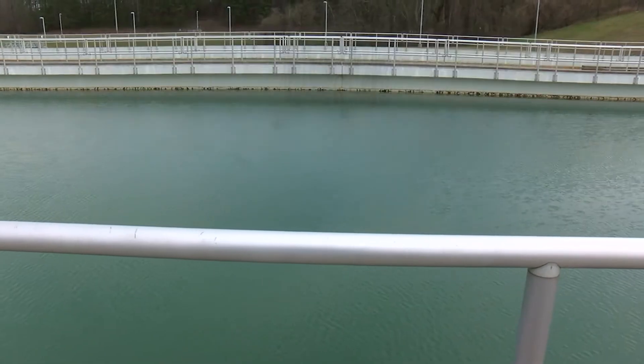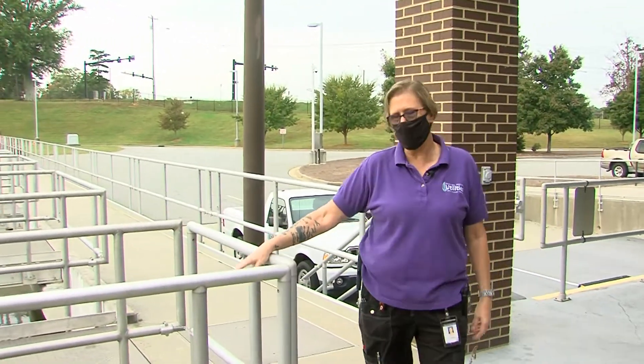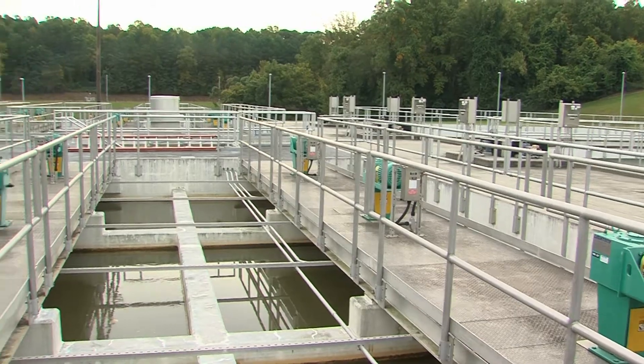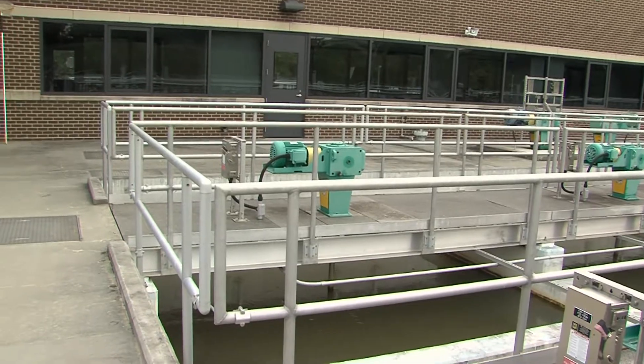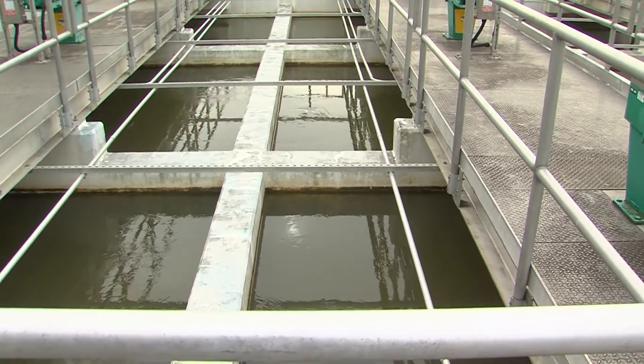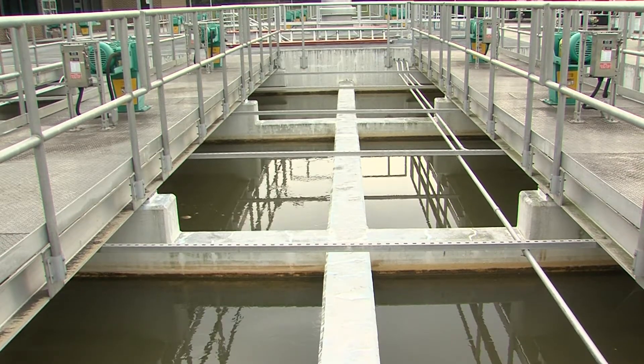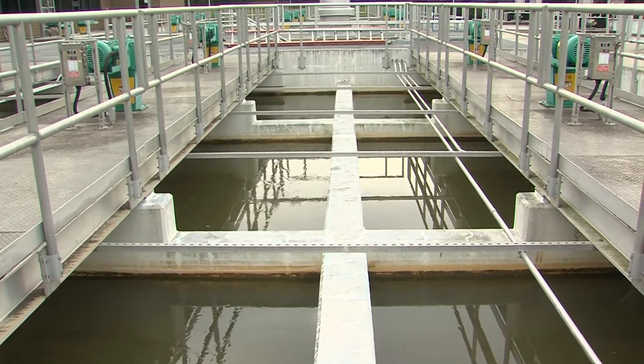This is where all the really cool stuff happens. Our first stop is the flocculators. This water is not ready for you to drink yet. These are flocculation basins. This process is actually stirring the water and the chemical together and causing a reaction in the water. The coagulation is actually chemistry at work — you're using positive and negative charges and making them want to come together and make bigger particles. This is the first stage and also the dirtiest stage. As we go down, you'll see the particles coming together and you can actually see the floc floating in the water. Floc is where the dirt particles have actually stuck to each other, and that's part of the reaction we're after. You can see where they're coming together and they make little tiny balls of stuff floating in the water. That is actually the dirt being separated from the water. Literally, you're taking dirt and making it want to stick together so it'll fall out, and you can actually see the process happening in each stage. It's really cool to watch — real life science experiments every day.